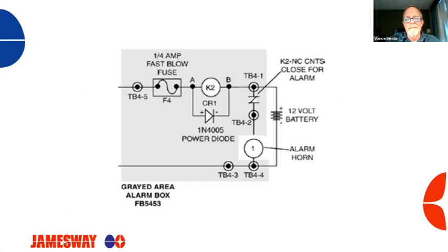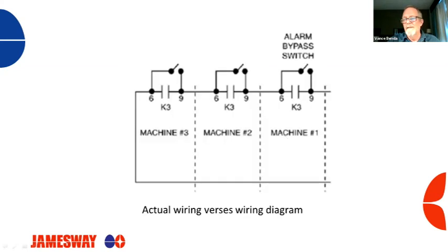I think we just covered everything on that gray box pretty good, but again, we want to be aware of the diode. We want to be aware that you're connected to normally closed contacts, and when we're building these alarm systems, we have to consider our power supply. And again, this loop is going to be considerably longer than what we have in these pictures, and that's what determines the size of the power supply required. And here again is your loop.